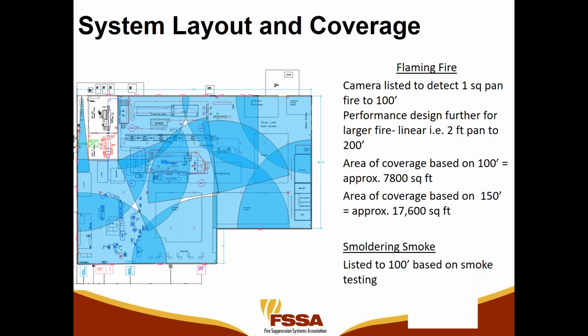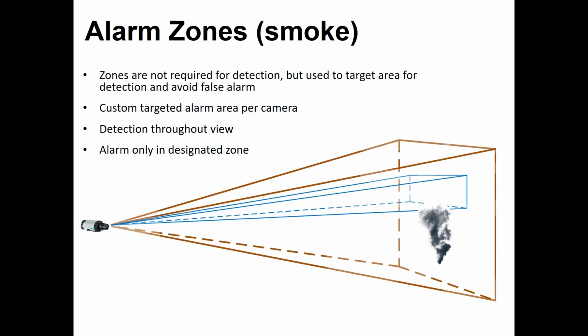With flame detection, we can go out and do a performance-based design to 150 feet, stating that we're detecting a larger fire, which would be an 18-inch pan fire in this case. We discussed zones. Zones are used to increase the sensitivity, allow us the highest sensitivity available and the lowest potential for false alarms. So a zone extends from the camera view out to as far as the camera can see.